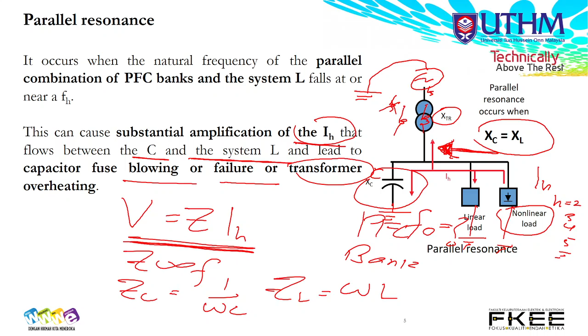Parallel resonance means C is in parallel with the source, in parallel with the L of the system, seen from the source of harmonic. In this case, looking at this figure, our C and L of the system are parallel. That's why we call it parallel.